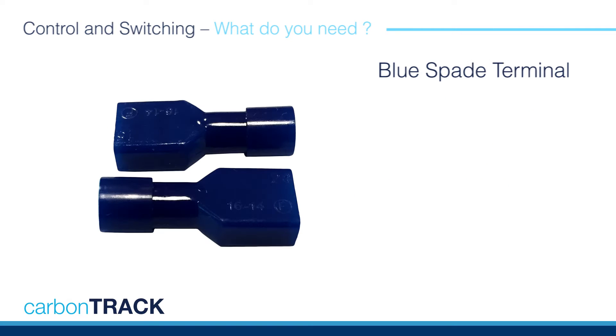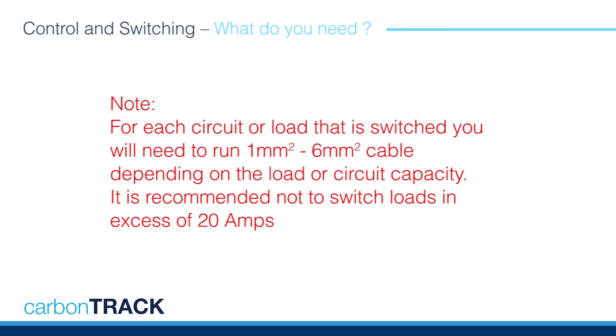The load is connected to the relay contacts via female insulated 6.3mm spade connectors. For each circuit or load that is switched, you will need to use one to six square millimetre cable dependent on the load or circuit capacity.